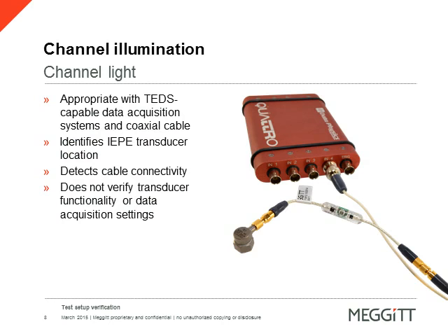This is performed by activating the channel light within the data acquisition system. For example, on the screen is a Data Physics Quattro. It allows the test technician to electrically reverse bias the LED through software. As you see, the 6-inch integral cable device is compatible with TEDS or non-TEDS transducers, including IEPE accelerometers and other IEPE modules. The channel light is inserted between the accelerometer and the normal coax cable, as it features a male and female connector. An integral LED light identifies the transducer's location.